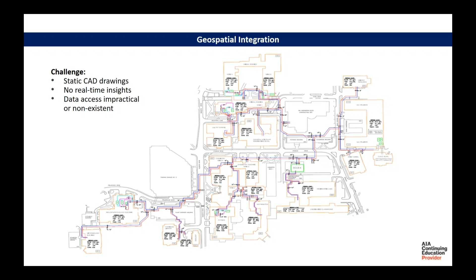And this is what we came up with. This visual includes data from multiple different systems: the SCADA system that controls the chilled water plant, and multiple automation systems controlling valves connected to the chilled water system, air handlers, and so on. It's all overlaid on this Esri map, and it's all real time.